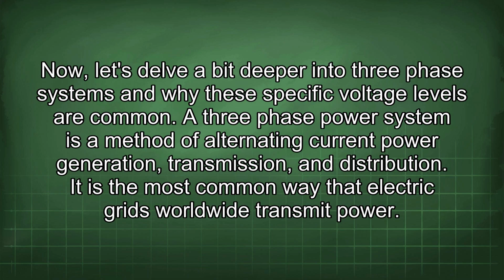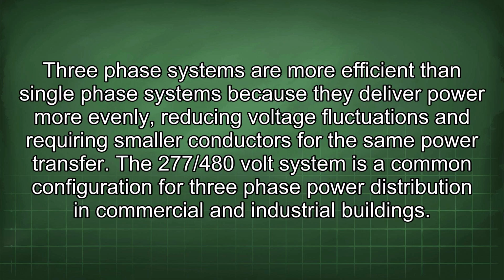Now let's delve a bit deeper into three-phase systems and why these specific voltage levels are common. A three-phase power system is a method of alternating current power generation, transmission, and distribution. It is the most common way that electric grids worldwide transmit power. Three-phase systems are more efficient than single-phase systems because they deliver power more evenly, reducing voltage fluctuations and requiring smaller conductors for the same power transfer. A 277/480 volt system is a common configuration for three-phase power distribution in commercial and industrial buildings.